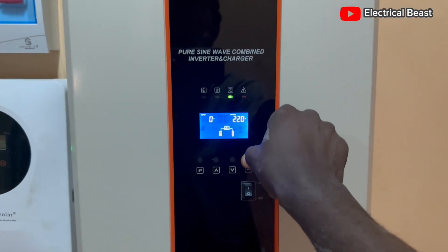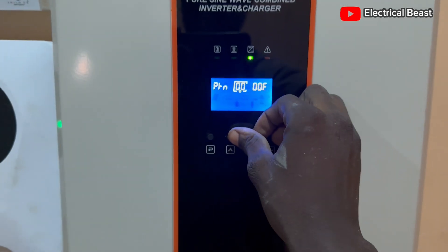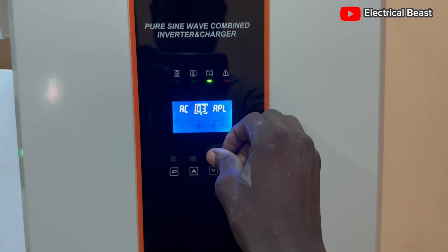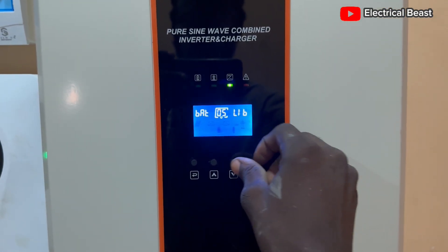The bulk charging constant voltage is 55.8V and the floating charging voltage is 55.5V. We are going to set these parameters on the inverter. Just come here, long press for three seconds, and it will take you straight to the settings.